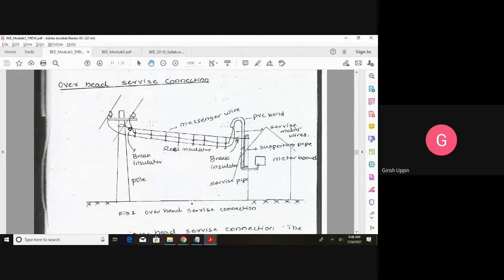Similarly on this side, we have an insulator called a break insulator, and then we connect it to this PVC bend. The two live wires will go inside this PVC bend, and through that it will go to the meter board. So this is the meter board. This is how the overhead service connection will be given.